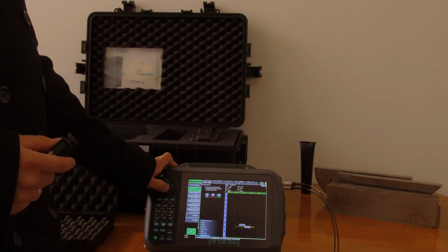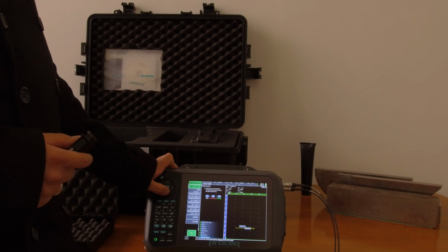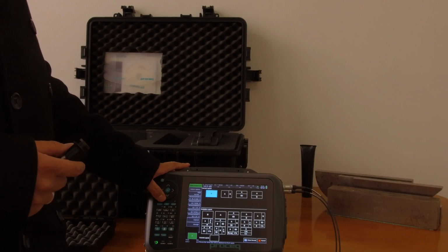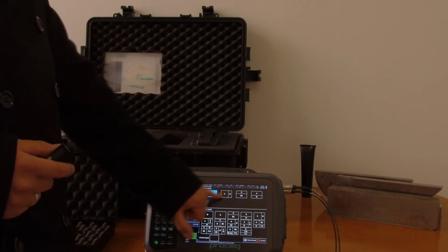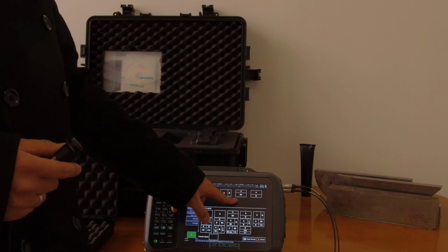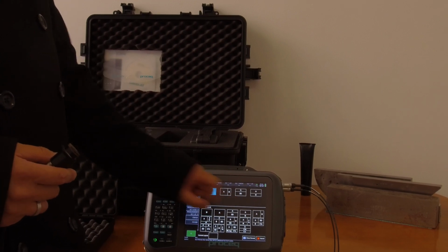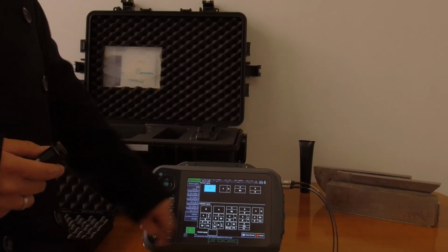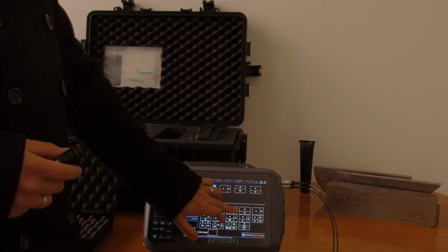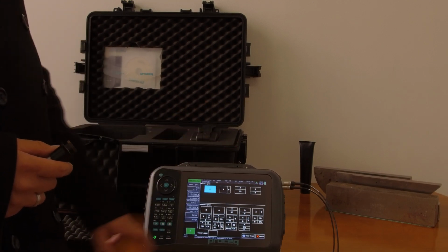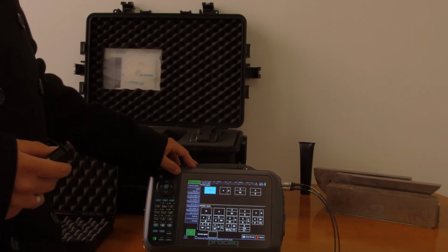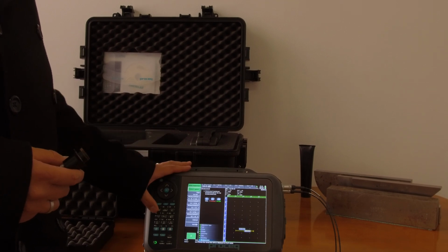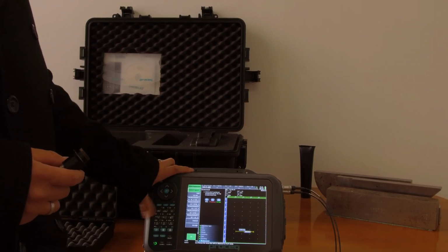Okay, then we come to this last setup. So there's a couple of things that we can nominate. We can select a layout, so we have the option of using an A scan with the B scan right next to it, an A scan with a 3D representation right below, an A scan with the B scan on the bottom. We can just look at a B scan. There's all sorts of things that we can do here. C scan based on percentage, C scan based on depth, all that good stuff. So you just choose the one that you think would be best for you. In this instance, I'm just going to stick to an A scan.